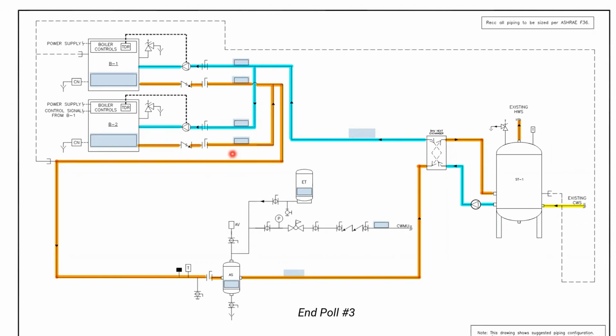There is no difference. Same appliance plus safety requirements. Yeah, that's not a true statement. ASME requires H stamp for boiler and HLW stamp for water heater. Yeah, very true. Boilers are rated to 160 pounds. Water heaters are rated to 80.